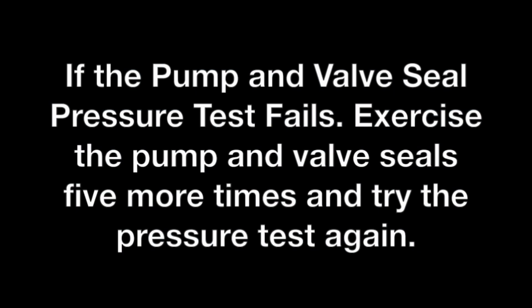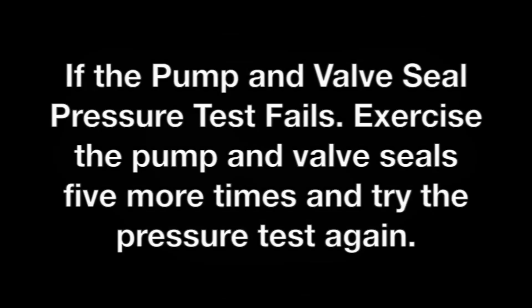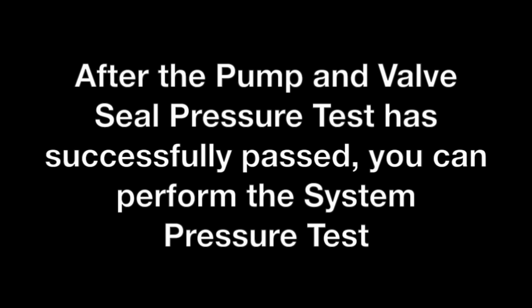If the pump and valve seal pressure test fails, exercise the pump and valve seals 5 more times and try the pressure test again. After the pump and valve seal pressure test has successfully passed, you can perform the system pressure test, which will test the integrity of the heated reactor and tubing to the mixing tees.